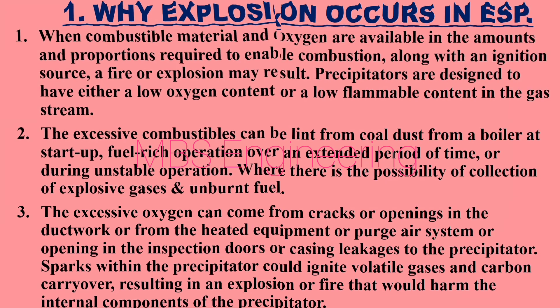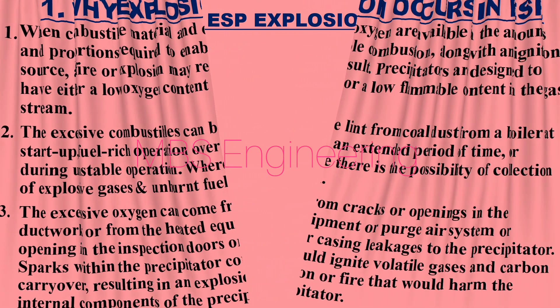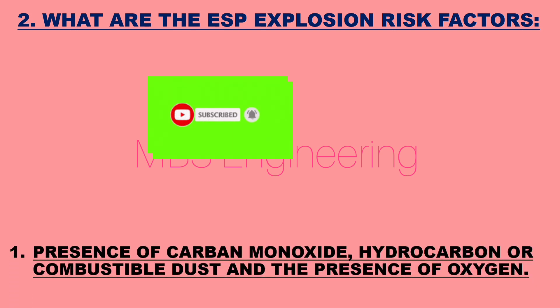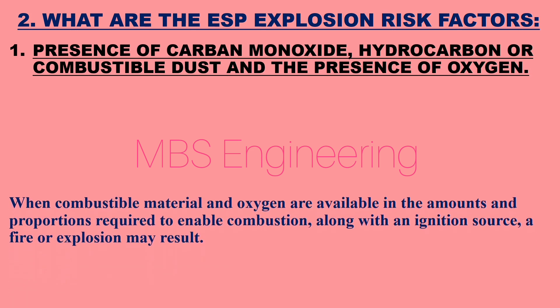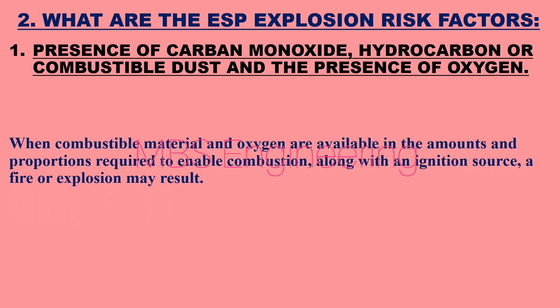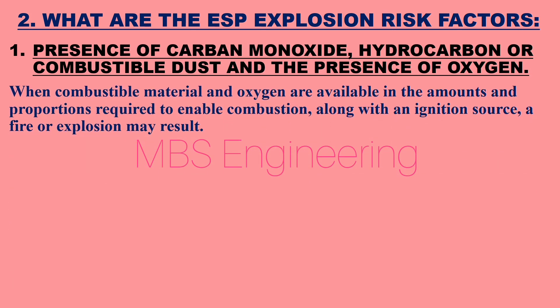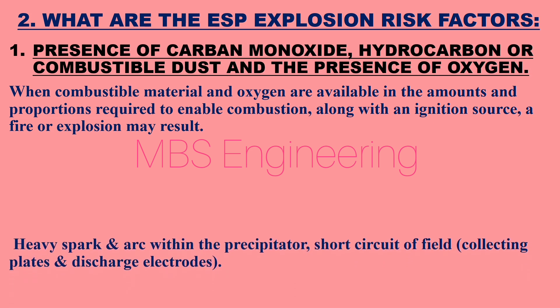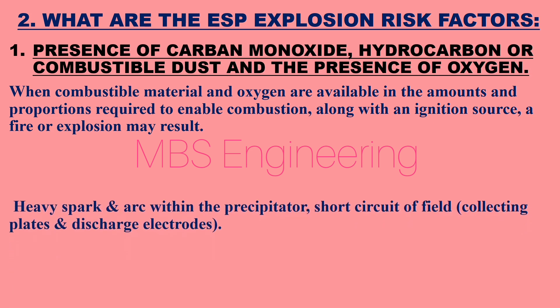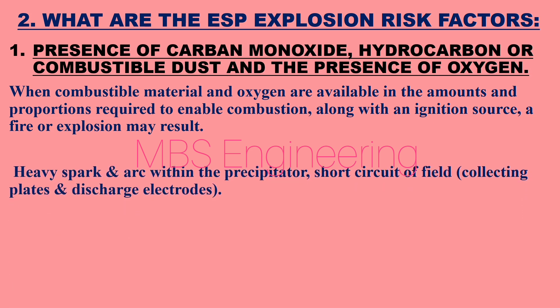Next, we will understand what the ESP explosion risk factors are. Risk Factor 1: The presence of carbon monoxide (CO), hydrocarbons, or combustible dust, along with the presence of oxygen. When combustible material and oxygen are available in the amounts and proportions required to enable combustion, along with an ignition source, a fire or explosion may result.